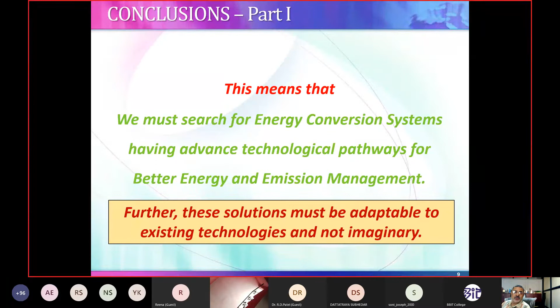Part 2 is what I am focusing on. Because 73% of electricity comes from coal in India, I am focusing on coal-based technologies with better energy and emission management. This is your present thermal power plant. There is a subcritical boiler producing steam at 150 bar and 540 degrees centigrade. It goes to the 3-stage turbine, HP, intermediate pressure and LP, and then goes back to your condenser, cooling tower, comes back to LP heater, HP heater, and back to the boiler.